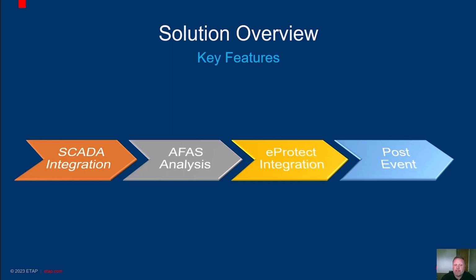ETAP AFAS provides a comprehensive fault analysis capability, which includes disturbance record analysis, fault severity analysis, and fault location. It also provides the as-found field sequence of operations and line impedance to furnish operators with a complete understanding of the fault response of the system. Through the as-designed ETAP sequence of operation, operators can compare the actual fault response with the anticipated response, which enables them to identify any discrepancies and take corrective actions. These capabilities enable organizations to quickly and accurately diagnose faults, reduce downtime, and enhance the reliability of their electrical systems.